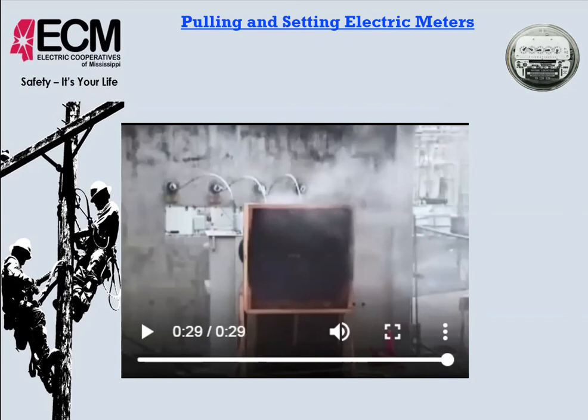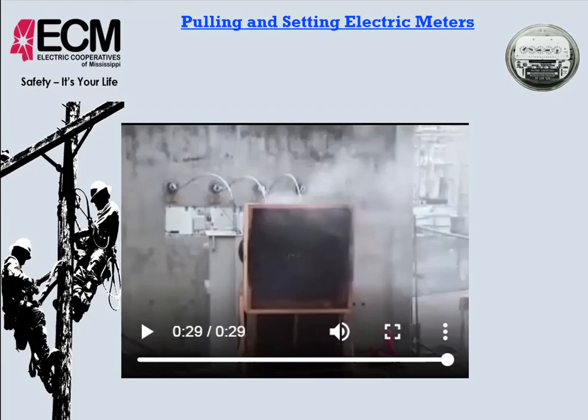Meters are not load break or load make devices. So if there's any load that could be picked up or broken, either that load needs to be removed or the entire thing needs to be de-energized. And here's an example of that. Trying to pull a meter could be the last thing you ever do. Watch this experiment. This is what can happen when you pull a meter and it shorts out at the base. Pretty, huh? The possible burns, eye damage, or even loss of life just aren't worth it.